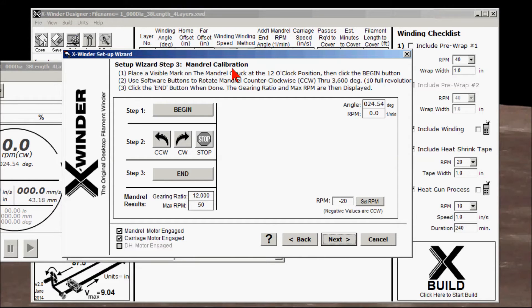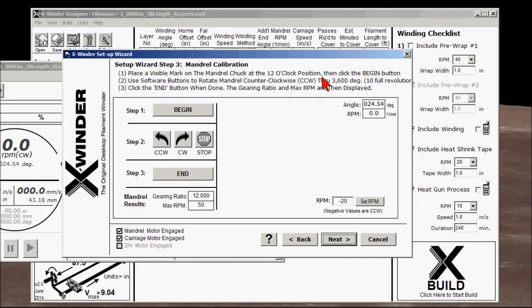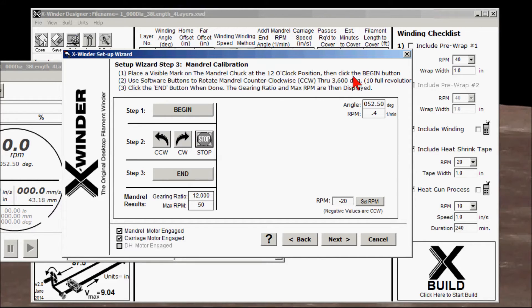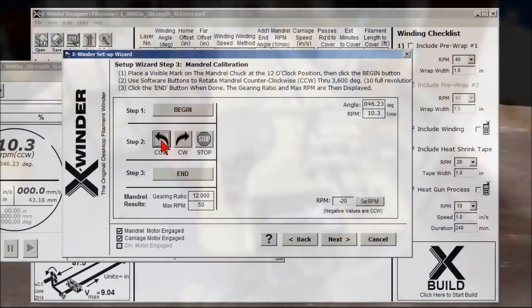Step three: mandrel calibration. Place a visible mark on the mandrel chuck at the 12 o'clock position. I've placed a manual mark, but it's not at the 12 o'clock position, so I'm going to move the actual position right to 12 o'clock, which is right about there — approximating for purposes of illustration. Then click the Begin button. I click Begin. Use the software buttons to rotate the mandrel counterclockwise through 3,600 degrees — that's 10 full revolutions. We'll start that.